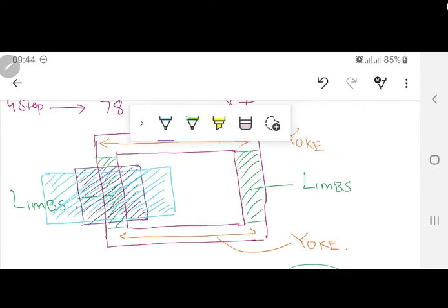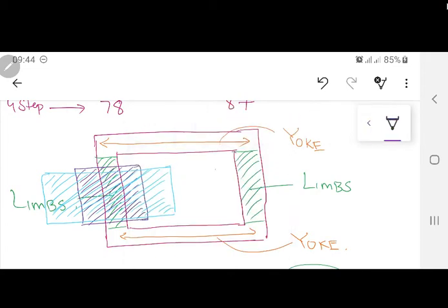Now on the other limb, same criteria over here. You will have first of all the low voltage winding, and I don't need to repeat that the low voltage windings are going to be made first. Why? Because they are closer to the core. The core is at neutral over there, so we don't want a flashover. Flashover means that we don't want the dielectric in between the core and the winding to actually conduct electricity. We want it to be a perfect insulator.